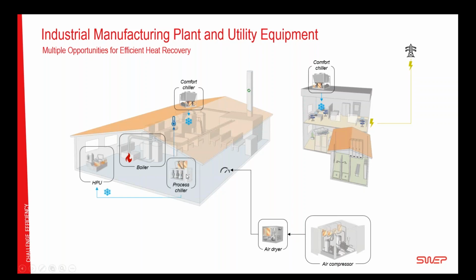We have the process chillers, cooling the process itself or any auxiliary system, in this case a hydraulic power unit, or HPU. Before we go there, in this very basic setup of machinery, we do see that brazed plate heat exchangers can be found as evaporators and economizers, and sometimes even condensers in the comfort chillers. We see them as oil coolers and air coolers in the compressors.